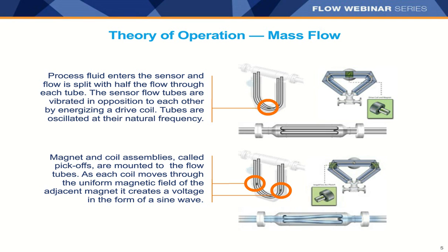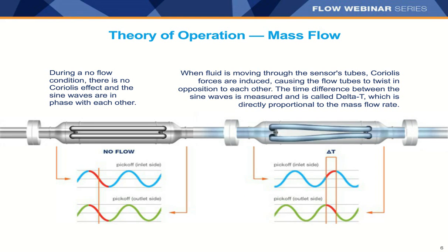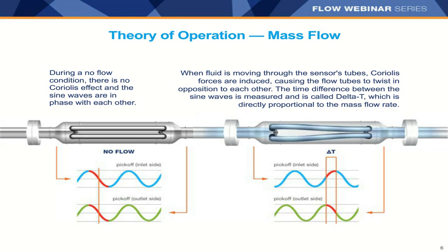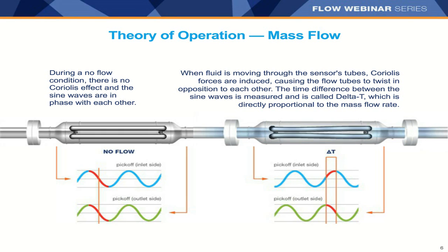On each side of the tubes are pickoff coils, mounted on both sides. Each pickoff coil moves through a uniform magnetic field adjacent to another magnet, which creates voltage in the form of a sine wave. With no flow conditions, there's no Coriolis effect and the sine waves are in phase. When fluid is moving through the sensor tubes, Coriolis forces are induced causing the flow tubes to twist. The time delay between the sine waves — called Delta T — is directly proportional to the mass flow rate.